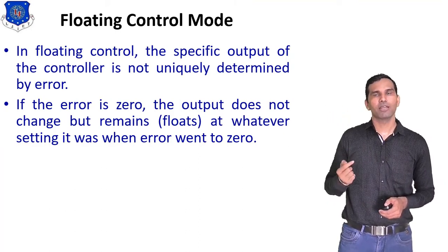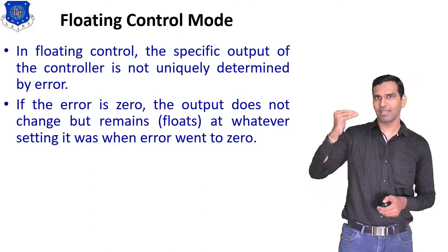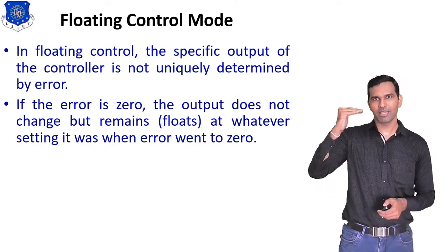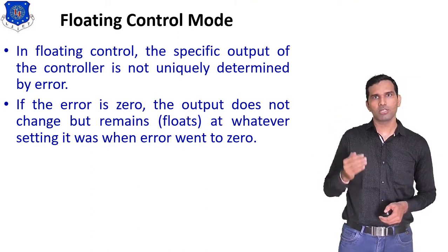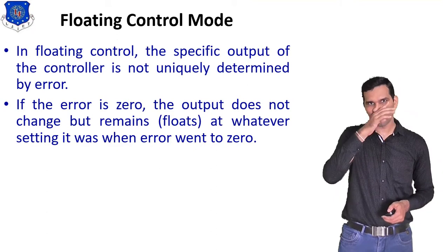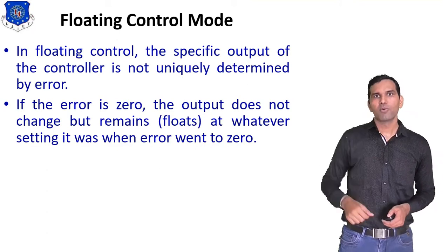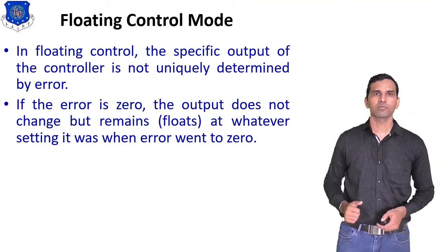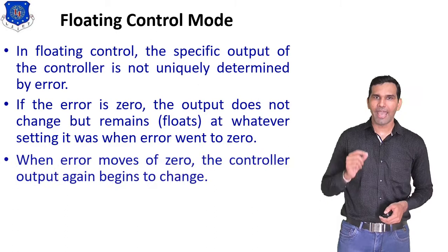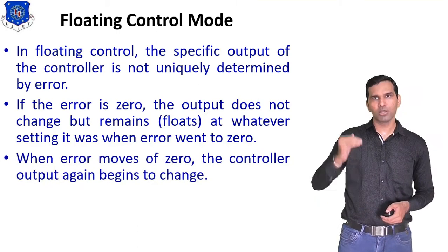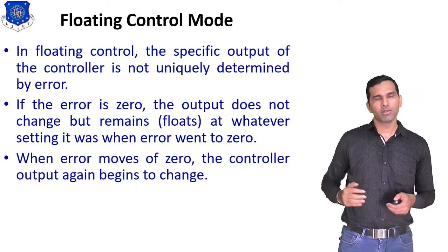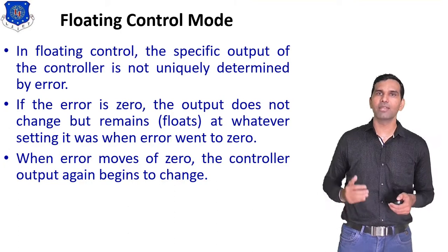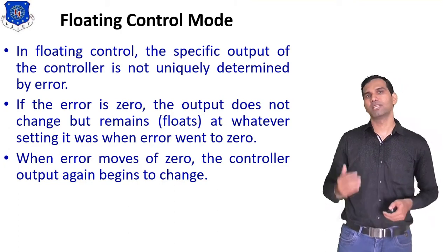The output remains at its previous position — whatever setting it was at when the error went to zero. This is the operation of floating control mode. When error moves away from zero, the controller output again begins to change.